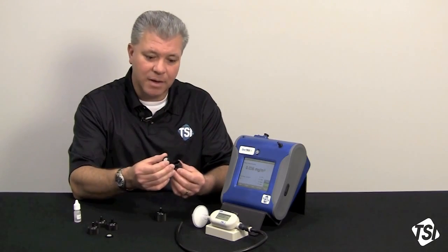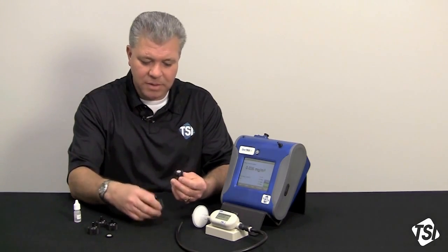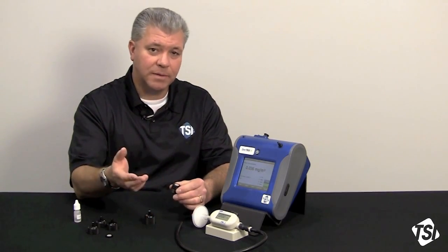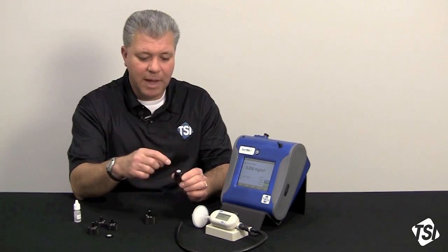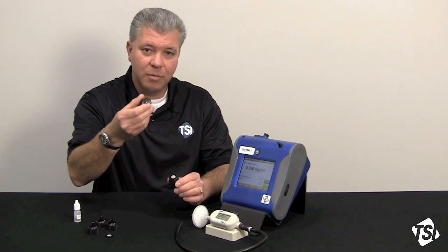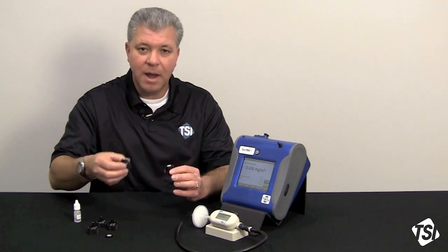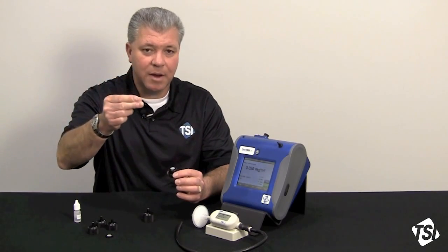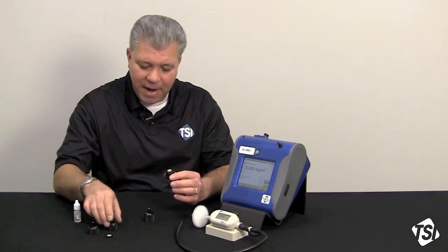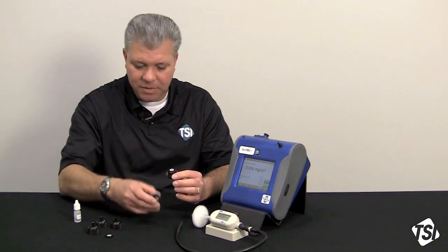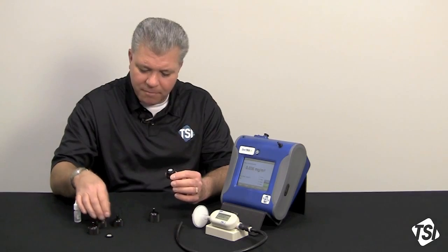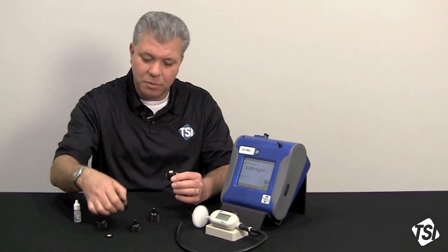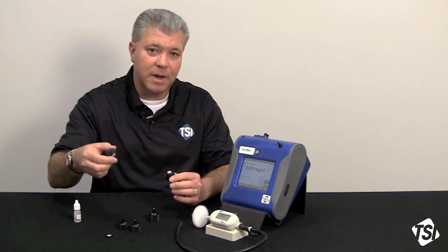An impactor is an inlet conditioner, and what happens is the aerosol comes through the inlet, and based on the flow rate at 3 liters a minute, the nozzle size will change to be a smaller diameter as you go smaller and smaller in particle size. So that 3 liters of air coming through, the velocity gets faster and faster. At PM10 it's 3 liters because it's a wide open tube. At PM4 you're looking at a little narrower tube, so the velocity goes faster. PM2.5 faster yet, and PM1 it's the narrowest inlet.